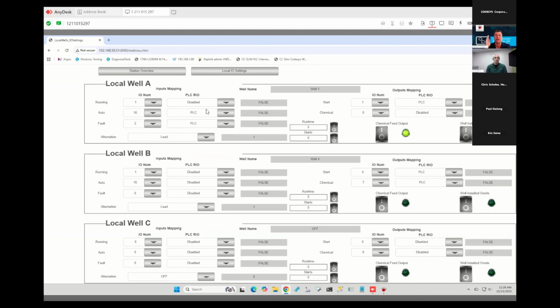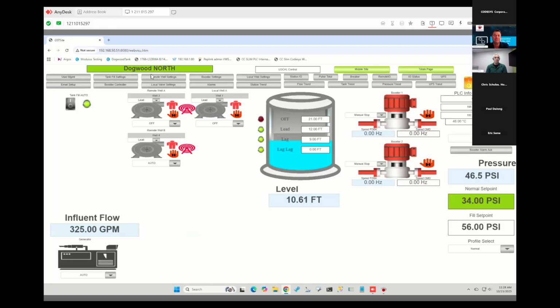It's just going to try to run it. If you add a running, what's going to happen? It's going to try to run it. And if it doesn't see a run feedback, it's going to fault and switch to the next one. So that also allows it to be very customizable in the field, because a lot of these are retrofits to existing stations. And when we get into the field, some of them do not have aux contacts wired up. They don't have anything but a go output. And we can make that happen by just simply remapping the IO.